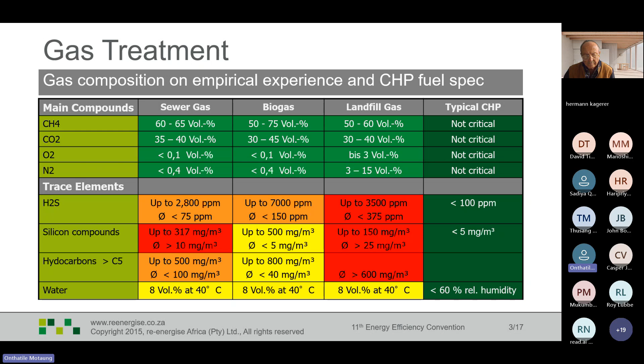Before we jump into the actual treatment itself, I have a few slides with pictures showing the impact of the trace elements I've looked at, so you understand why we need to pay special attention to removing or limiting them so they don't inhibit operation of the CHP. Here we have a blocked silencer at the exhaust due to siloxanes.